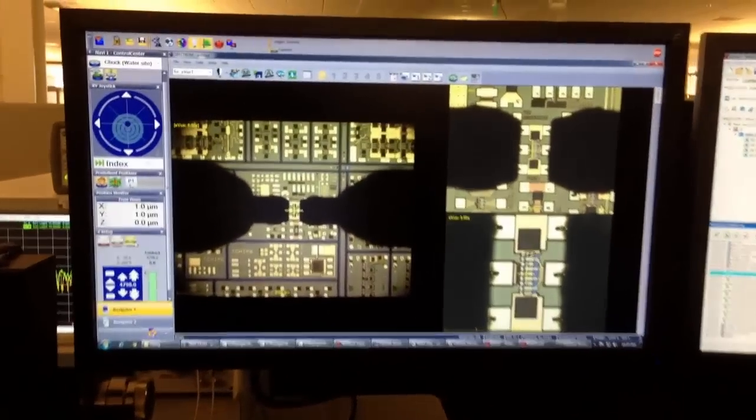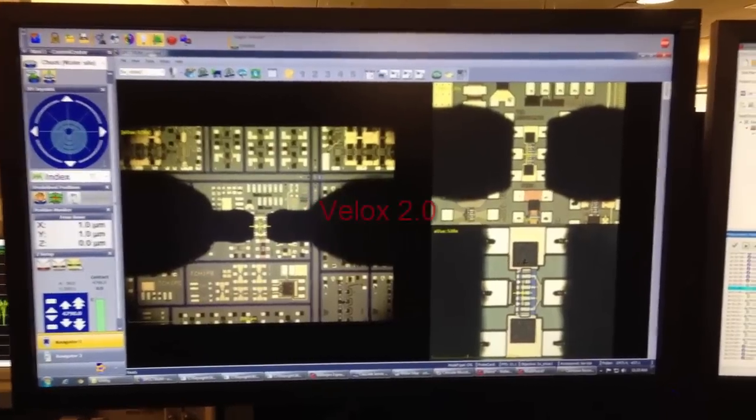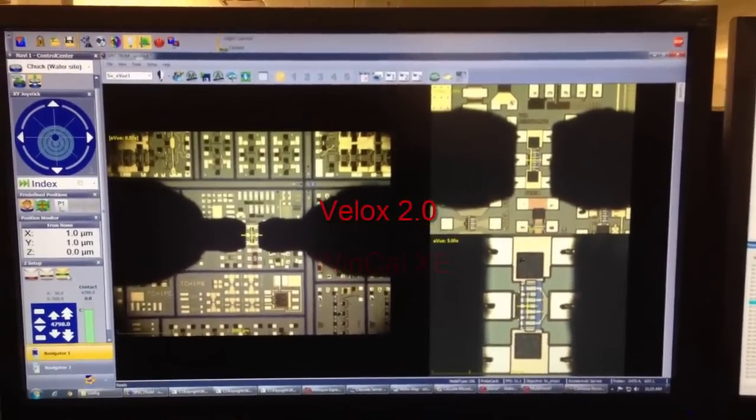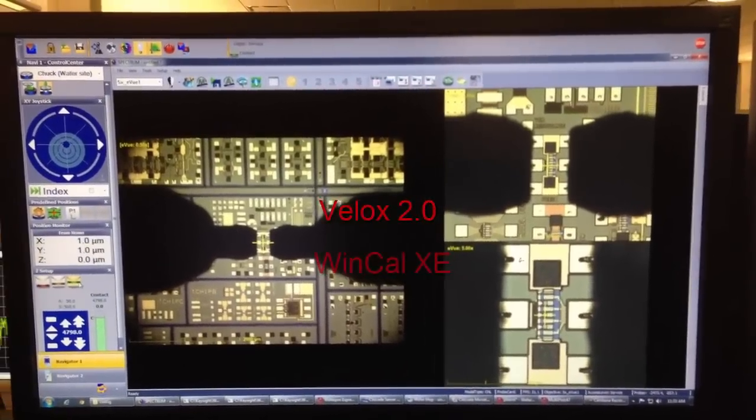In this system, the probe station chuck positioning, the wafer temperature and the camera are controlled by Cascade software Velox. The RF calibration is controlled by Cascade WinCal XE software.